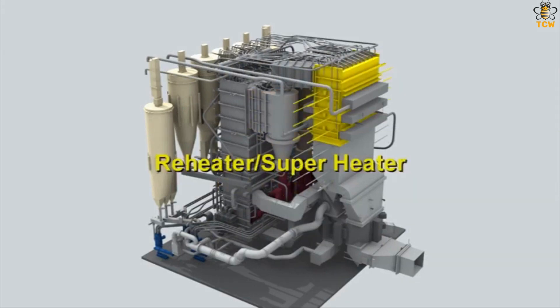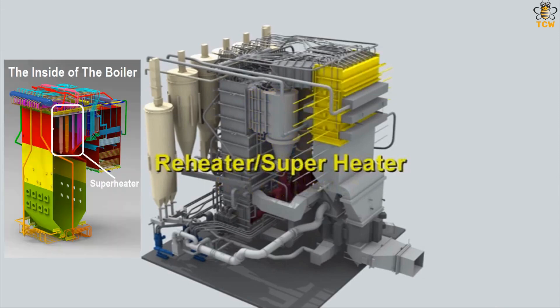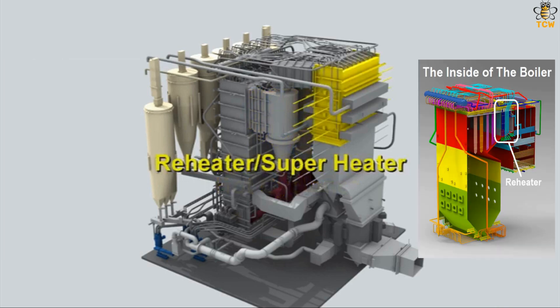The next components are the superheater and reheater. The superheater is an arrangement of pipes in the boiler used to convert saturated steam or wet steam into superheated steam or dry steam by absorbing heat from hot coal combustion gases at very high temperatures. The reheater is an arrangement of pipes used to raise again the temperature of steam coming out of the turbine, since the hot gas passing through the superheater is still quite high in temperature. This steam is then flowed into a low-pressure turbine.